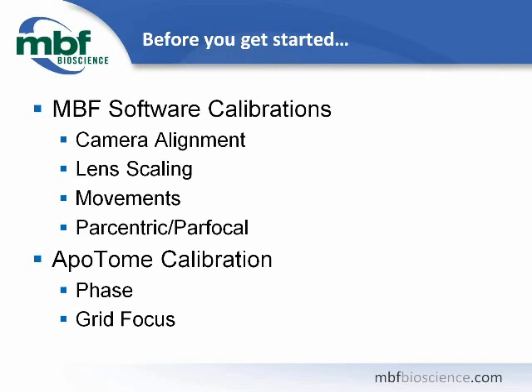In addition, to use the ApoTome, which is only available through Zeiss, you need to calibrate it as well. There are two phases of calibration: phase calibration and grid focus.